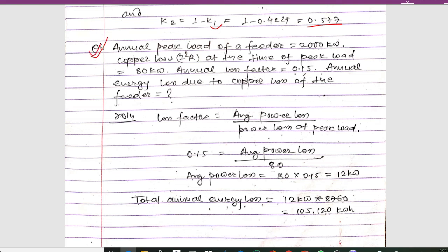The annual peak load of a feeder is given as 2000 kilowatt. The copper loss (I²R) at the time of peak load is 80 kilowatt, and the annual loss factor is given as 0.15. We have to determine the annual energy loss due to copper loss of the feeder. Loss factor = average power loss / power loss at peak load.